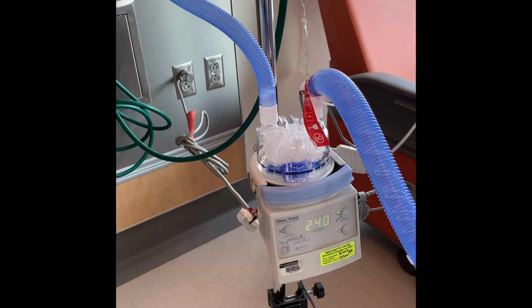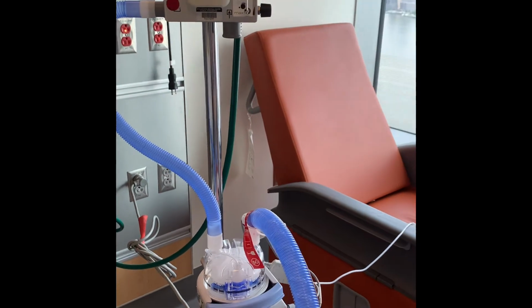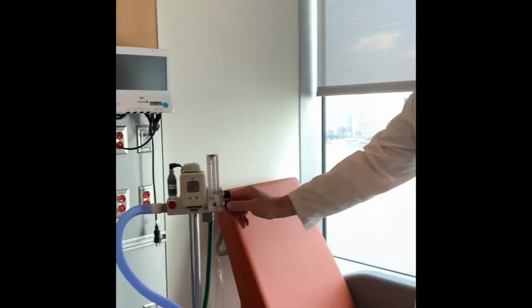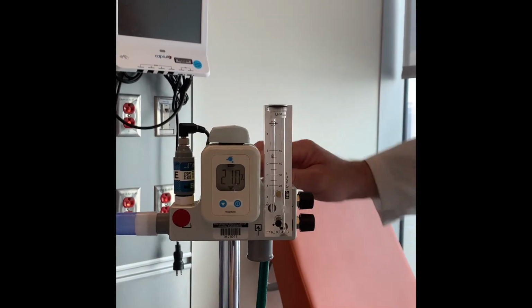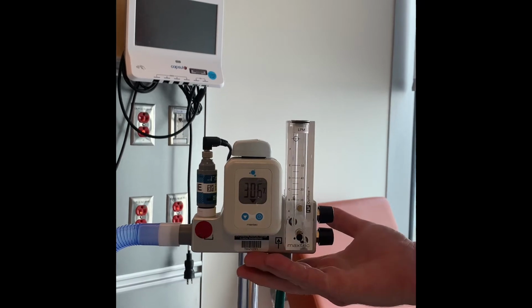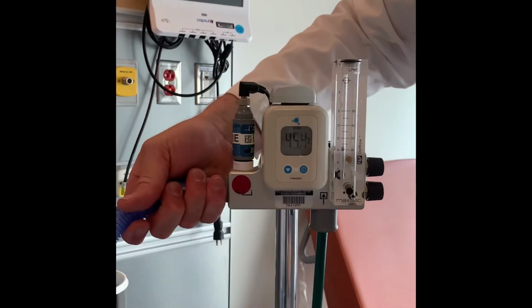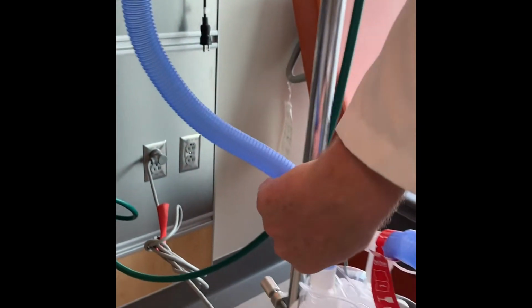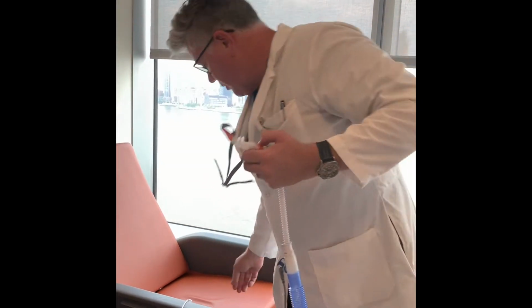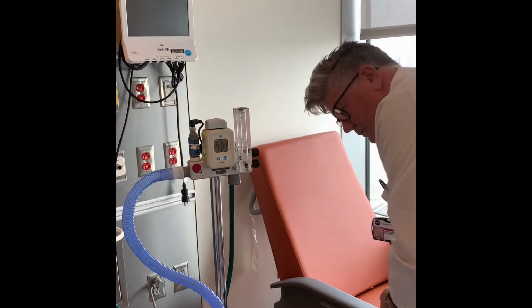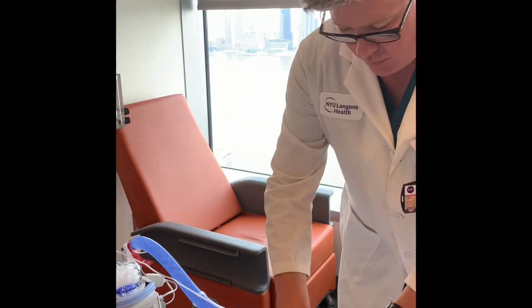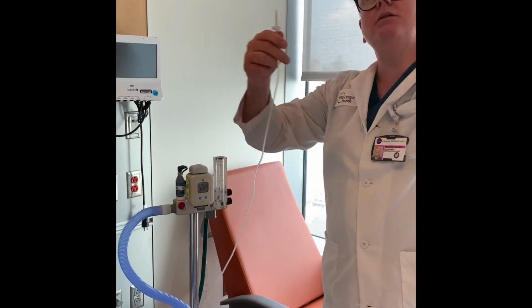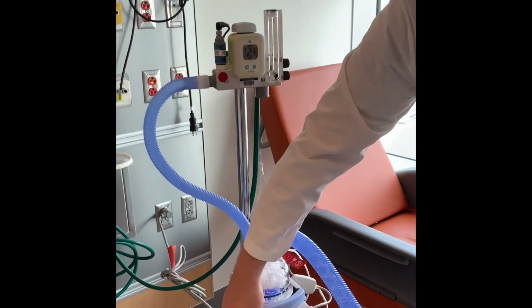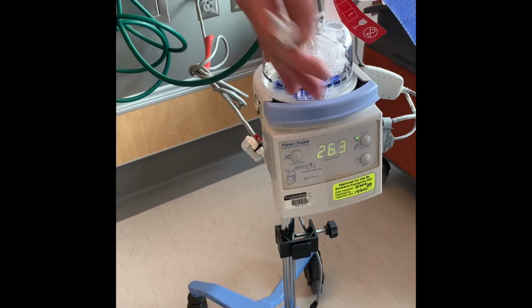So if we go over all of this, you have the machine. We have oxygen, we have flow. Okay, so air is being given, oxygen is being given, air is being entrained. It's coming out of here. It's going through this tube, being humidified, coming down, humidified, and being delivered to the patient. And the humidification process, all we're doing is we have a water bag that's spiked, so it's gravity-fed water into this chamber. This device right here is going to heat the water to create humidity for the patient.